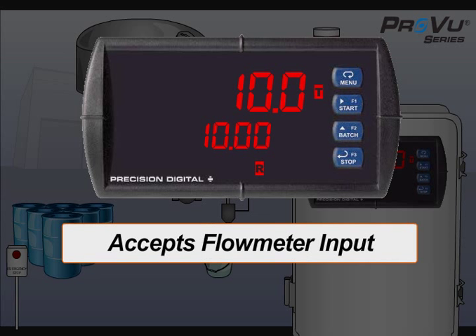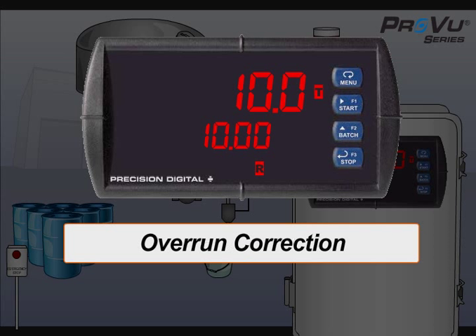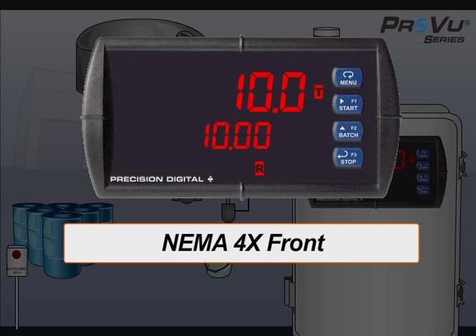This ProVu accepts the flow meter input, has four relays to control the system components, and uses its overrun correction feature to maintain consistently accurate batches. The display is set to show the batch total and preset. The NEMA 4X front is ideal for this application as the solution has the potential to splash and spill.